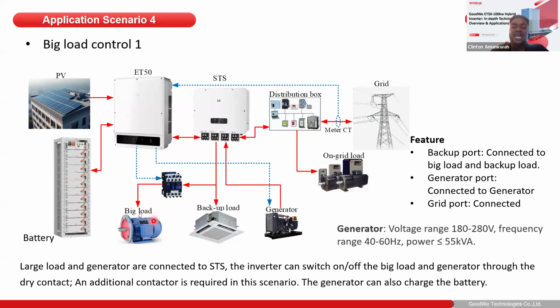So with this, you can highly control how your battery discharges to this big load. Very simple, with just the introduction of a contactor, a signal cable, and a very few configuration settings. And then you are able to achieve big load control with the GoodWe ET 40, 50, and 100 kilowatt hybrid inverters.